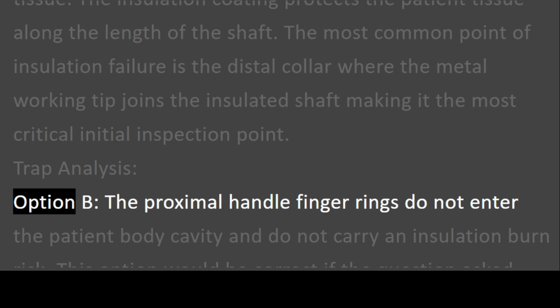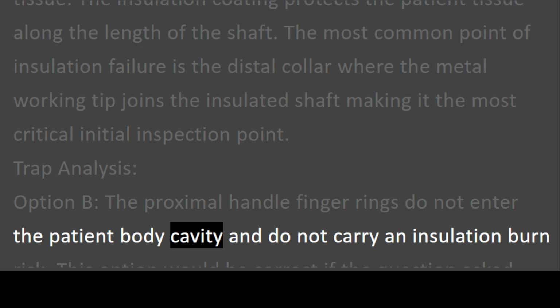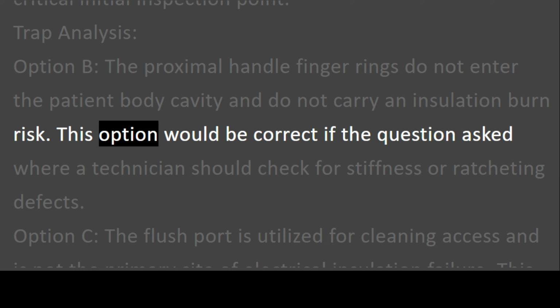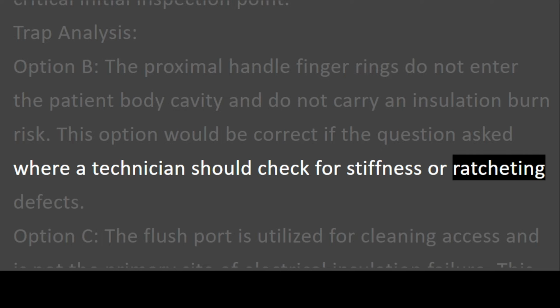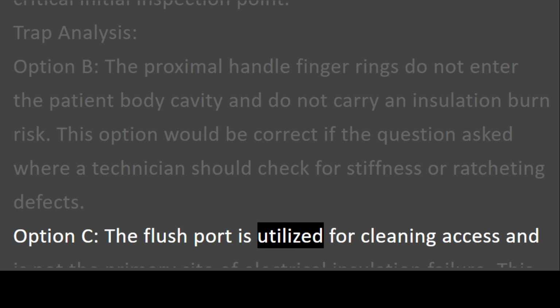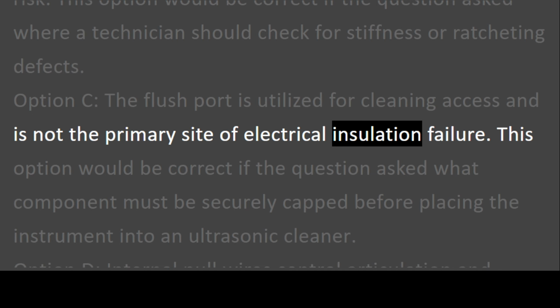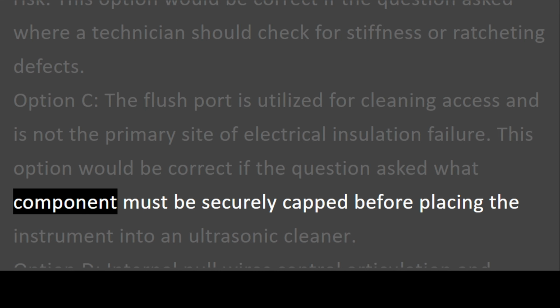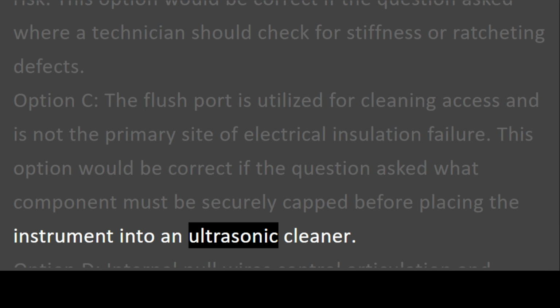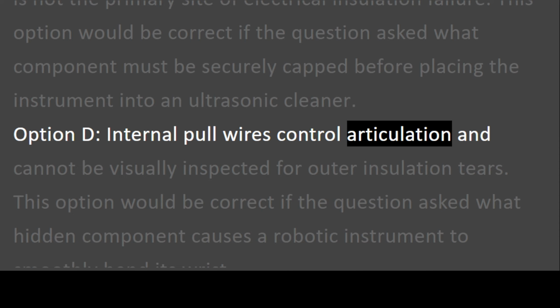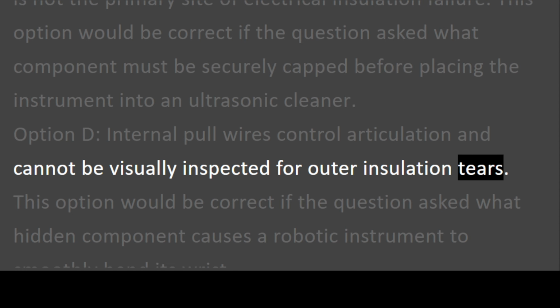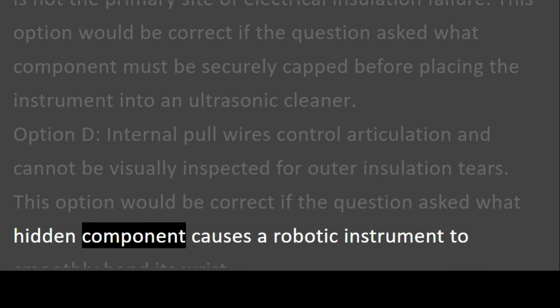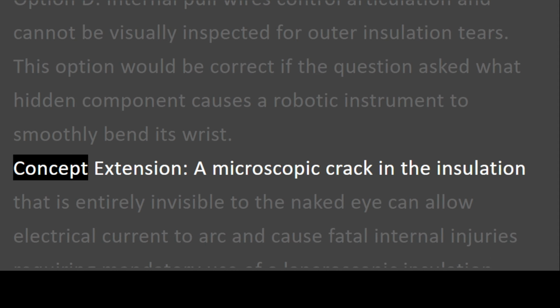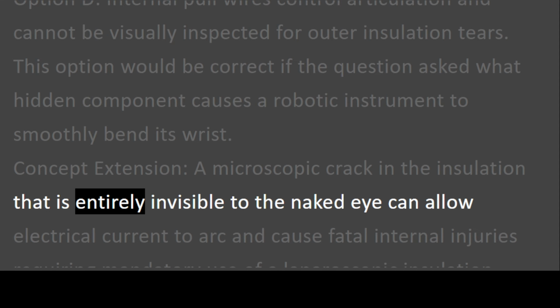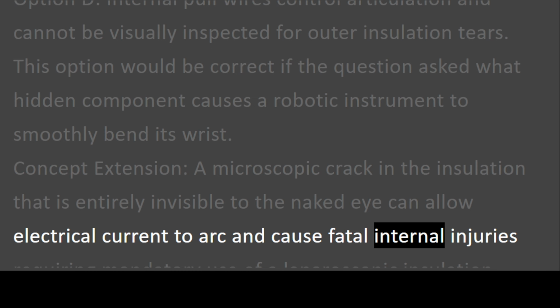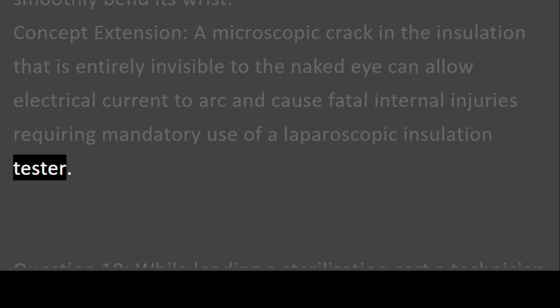Trap analysis. Option B. The proximal handle finger rings do not enter the patient body cavity and do not carry an insulation burn risk. This option would be correct if the question asked where a technician should check for stiffness or ratcheting defects. Option C. The flush port is utilized for cleaning access and is not the primary site of electrical insulation failure. This option would be correct if the question asked what component must be securely capped before placing the instrument into an ultrasonic cleaner. Option D. Internal pull wires control articulation and cannot be visually inspected for outer insulation tears. This option would be correct if the question asked what hidden component causes a robotic instrument to smoothly bend its wrist. Concept extension. A microscopic crack in the insulation that is entirely invisible to the naked eye can allow electrical current to arc and cause fatal internal injuries, requiring mandatory use of a laparoscopic insulation tester.